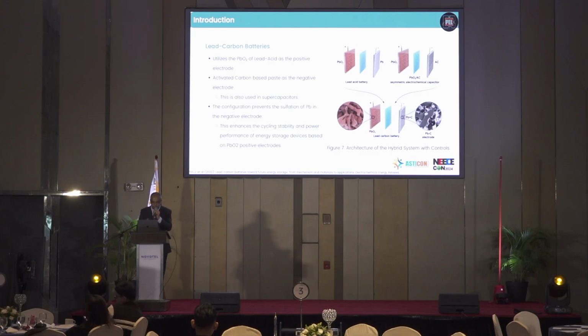So recent developments would be advancements in the performance by adding carbon in the negative electrode. This gave rise to the lead-carbon batteries. They would still have lead oxide in the positive electrode and activated carbon in the negative electrode. This is the same technology used in supercapacitors. This addition to the lead-based battery actually prevents the sulfation in the battery, so this would enhance the overall performance of the battery.